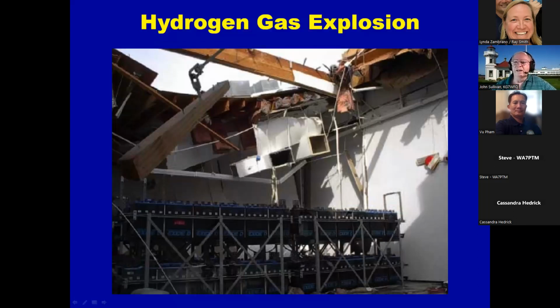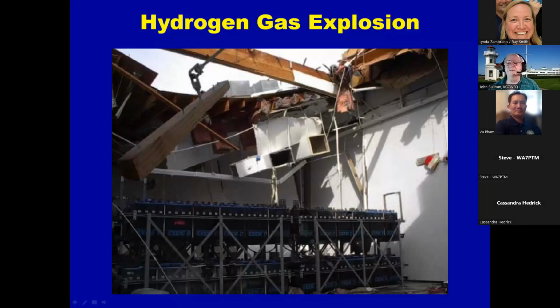Apparently the 911 callers who reported the explosion said they had also been hearing an alarm going off for 3 days. So apparently the alarm was just a local alarm, not monitored anywhere. Given how slowly batteries generate hydrogen gas, it's likely the batteries were charging for a long period of time with no ventilation, and the detector did its job - it sensed the hydrogen gas buildup, but nothing was done about it.